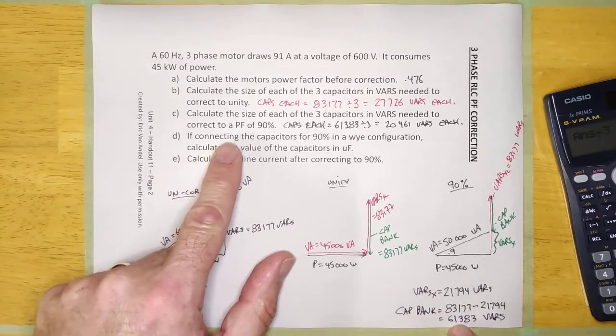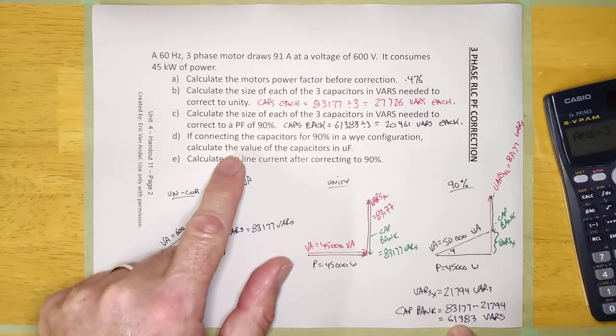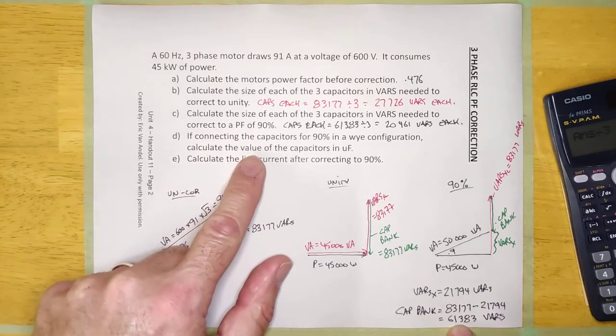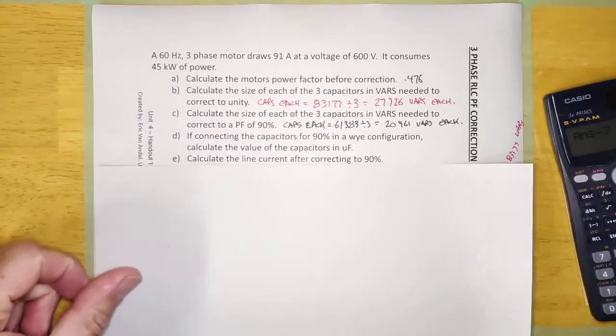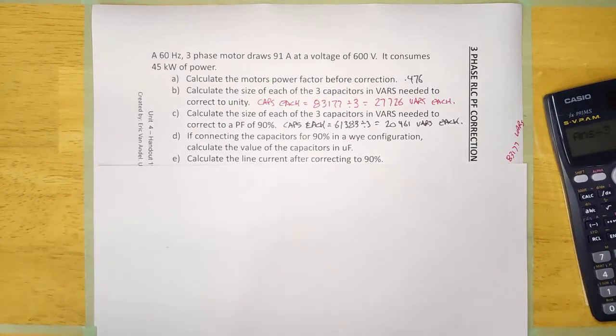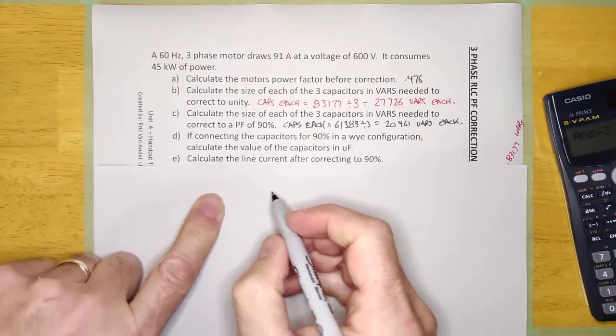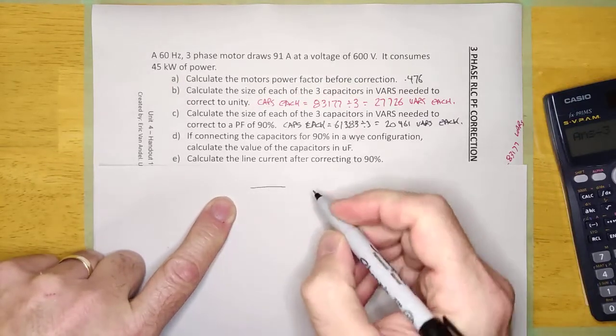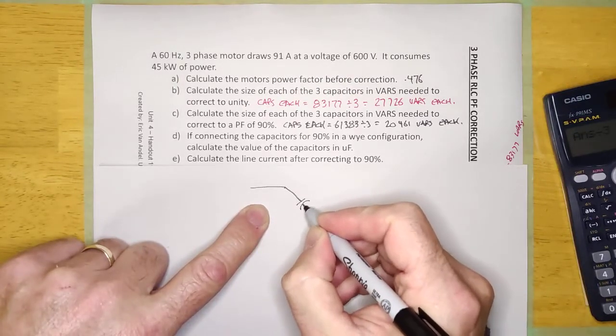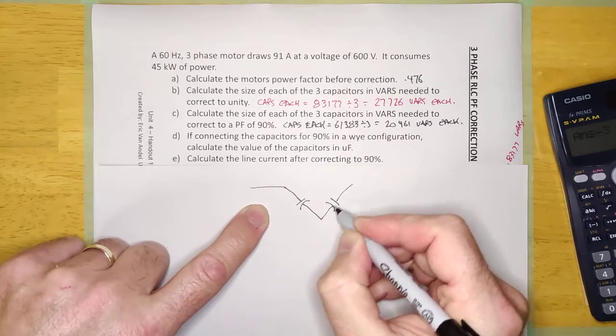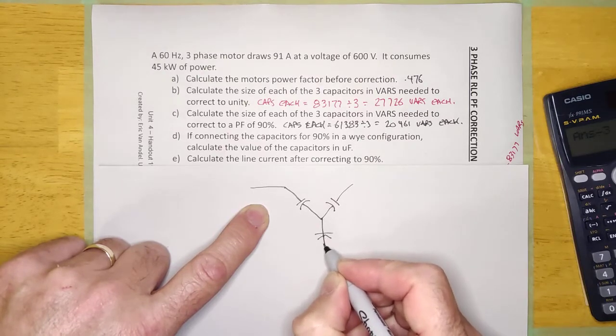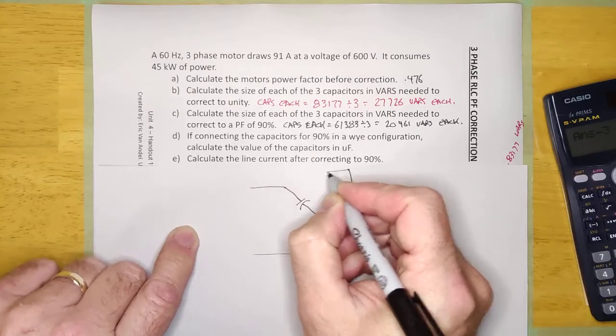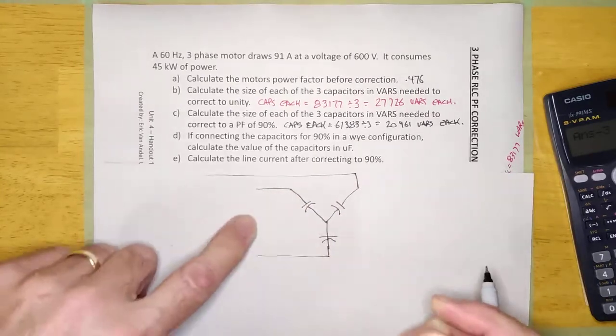We just figured out the size of the capacitors that we would need to correct this thing. And here, look at this. If connecting the capacitors for 90% in a Y configuration, calculate the value of the capacitors in microfarads. Well, let's take a look at that one for a second. I'm running out of room here, so I'm going to get another piece of paper out here. We've got some sort of three-phase motor here, and it looks like it's telling us that we are connecting our capacitor bank that we just calculated to correct to 90% like this in Y. And so, it's in parallel with whatever load that is out here.